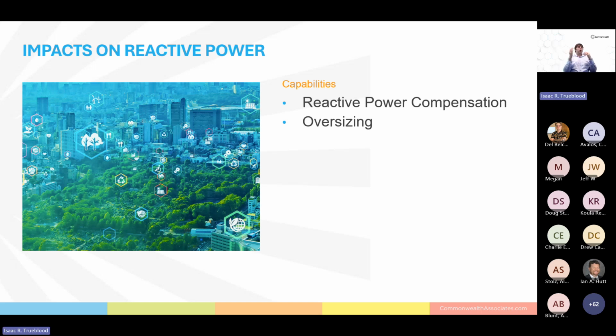So, what are mitigation options for achieving these MVARs? For some sites, reactive power compensation is the best solution. This usually involves adding capacitors or inductors, occasionally the type that switch on and off, and this will help to provide additional reactive power to the distribution system when needed, helping maintain voltages at the required levels.